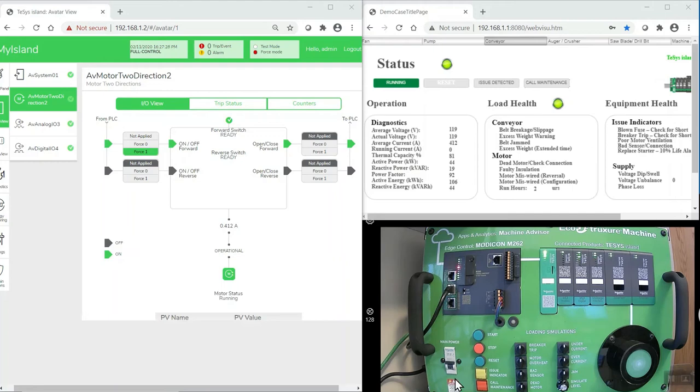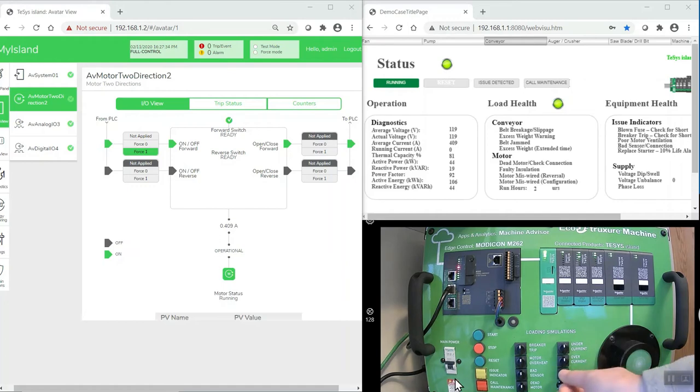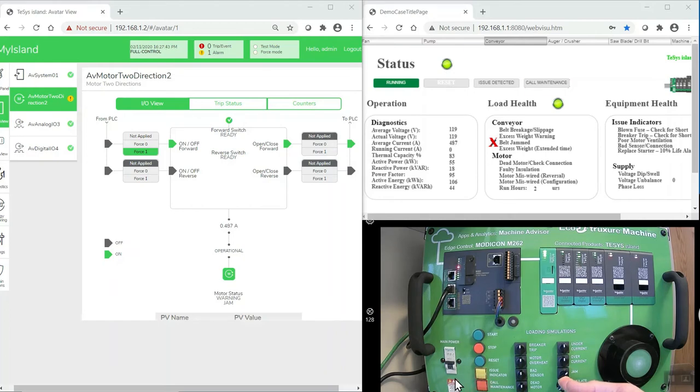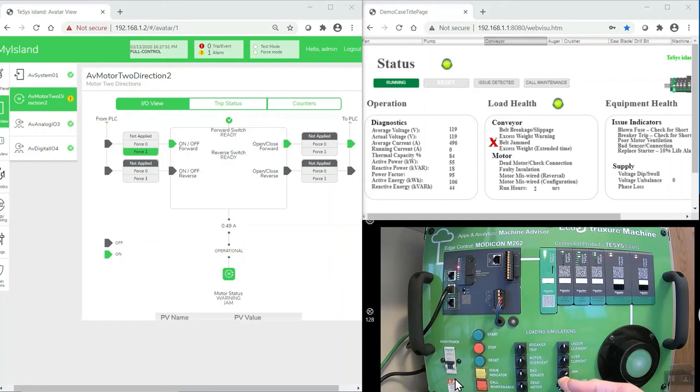With the motor running on the demo station, we'll turn the jam switch to simulate a jam alarm. With the jam alarm simulated, you can see on the left-hand panel that the motor is still running, it's drawing about 400 to 500 milliamps, and the jam warning is on. In the panel to the top right, you can see that we've now signaled that there's a potential for a belt jammed, and we have a flashing call maintenance light. You can see on the demo itself, the light is flashing.